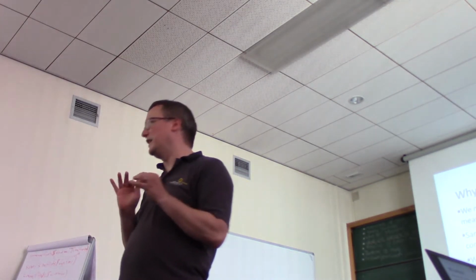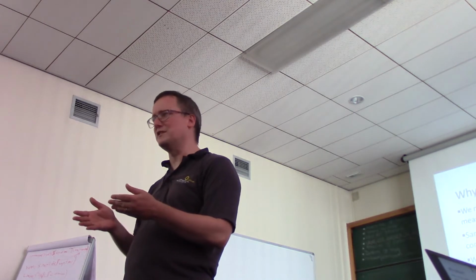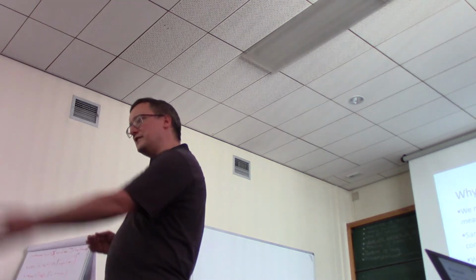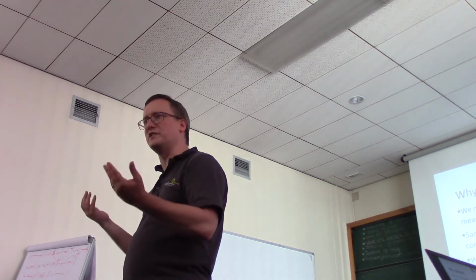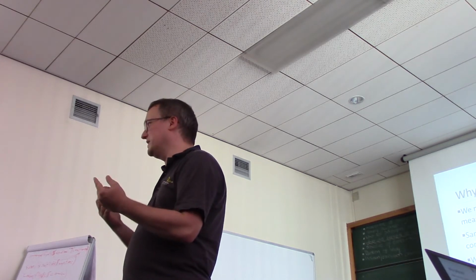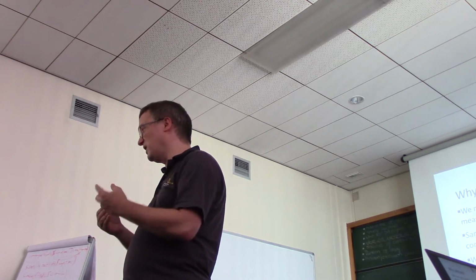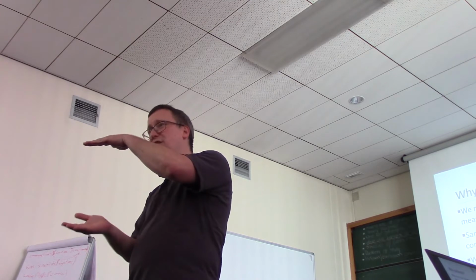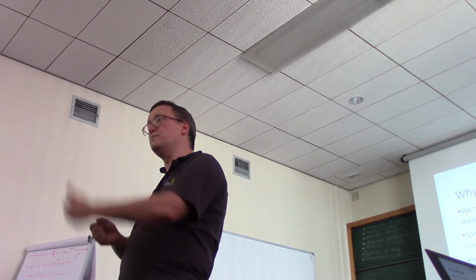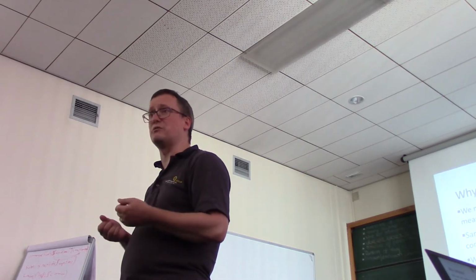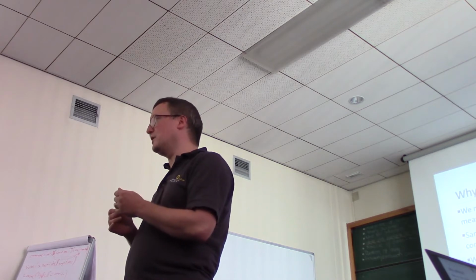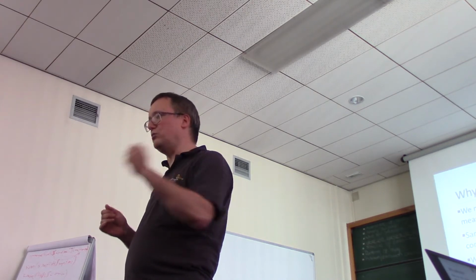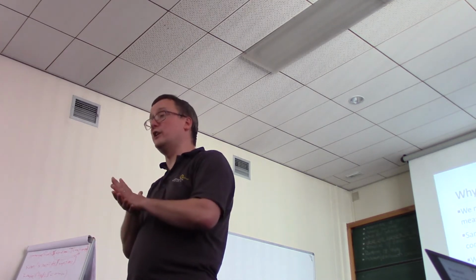Now, a lot of people, I think, get that the calibration series is intended to say, with this much light, you have this much quantity, right? But we would also like to have a model, if you will, on how much variation there is between these measurements and the quantities they're supposed to represent. If the calibration curve samples are all right on the line, then we have a low variability of measurement.